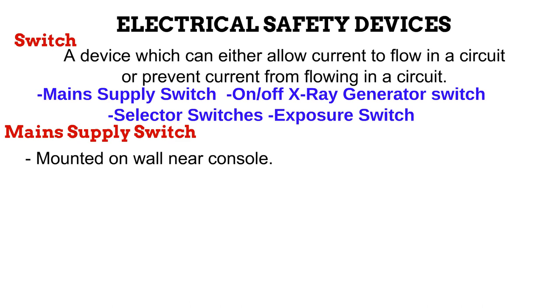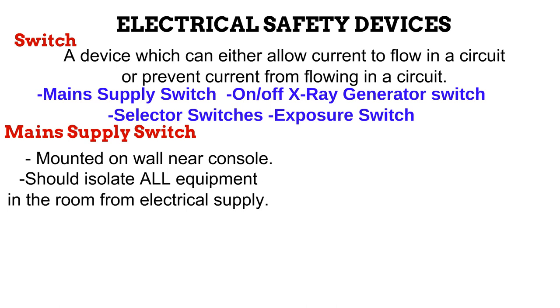The main supply switch is usually mounted on the wall near the console, and should be easy to access with nothing placed between the radiographer and the switch. The main supply switch should isolate all equipment in the room from electrical supply, meaning every piece of equipment in a diagnostic radiography room should be under the control of one main supply switch. If you have an X-ray machine and a skull unit in one room, they should both be controlled by one switch. In an emergency, turning off the single main supply switch gets everything done quickly — if there were multiple switches, it would take more time, and in an emergency, every second counts.